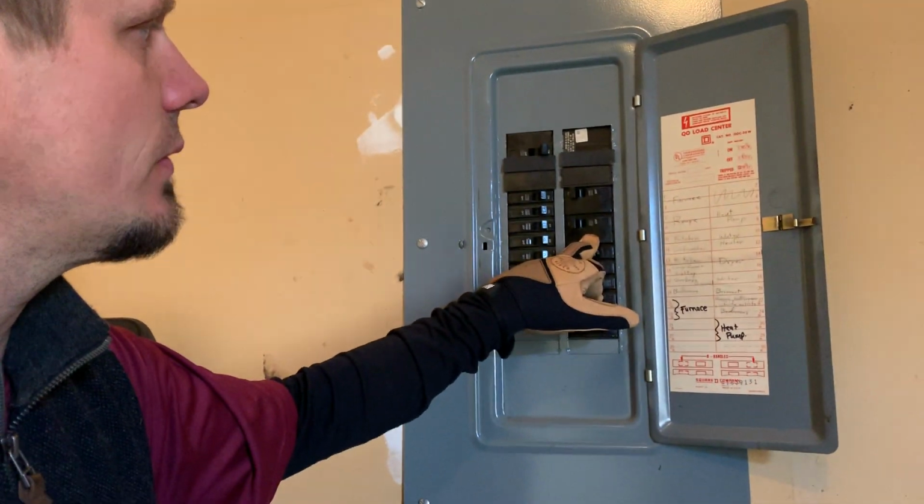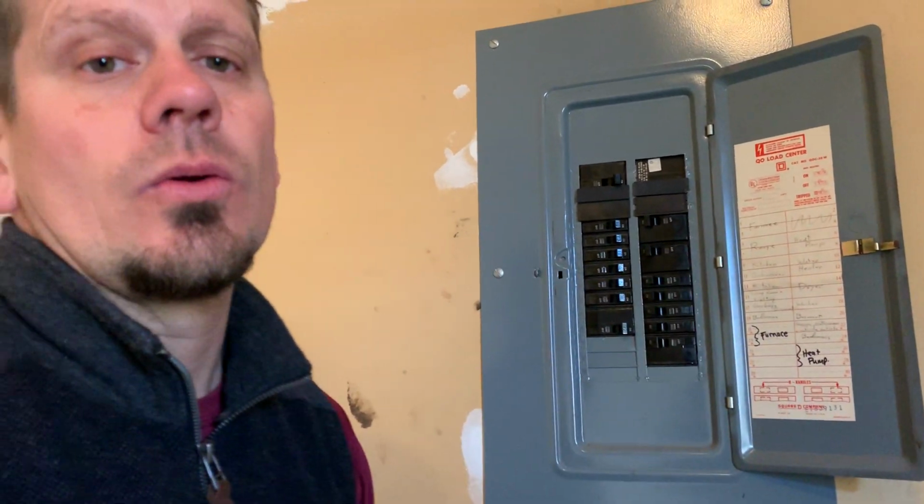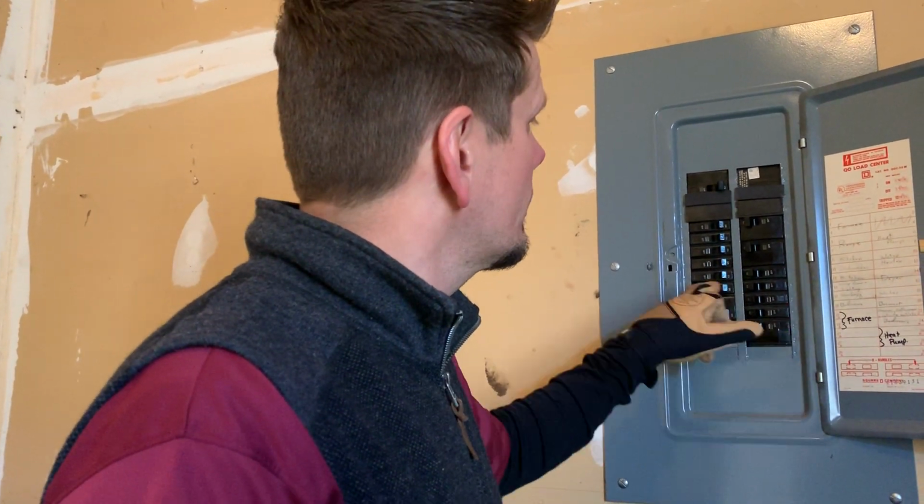And then you have to remember there's a 4,500 watt hot water heater as well, and that's going to be running about 18 amps. Those are elements, so they run the full amount of current until they're satisfied. Until that tank is filled, it's not going to slow down and stop with the thermostat. It's important to get those items changed out, especially your hot water heater, which can be rusted or just not heating as well. By the way, those hot water heaters can have two elements, a dual system. You don't take 4,500 times two, but you have to keep in mind it's both together, and dividing that by 240 volts, you're right around 20 amps. So if you add that to the 30 and 30, you could be consistently running close to 80 amps. Keep that in mind.